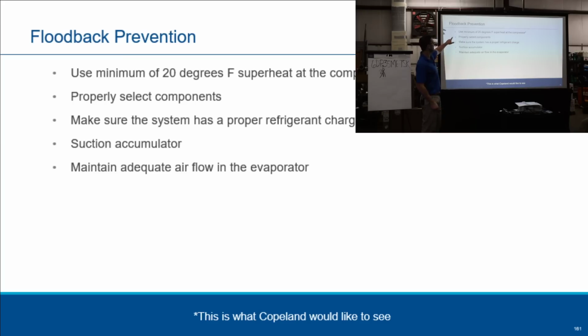Okay, things to prevent flood back. Copeland recommends 20 degrees superheat at the compressor. You can't always get 20 degrees superheat, right? If you have a small plate chiller with the TX valve or the electronic expansion valve, and you have 2 feet to the compressor and you're running at 10 degrees superheat, are you going to pick up 10 degrees superheat to that compressor? No, you're not, right? So, okay, it's running at 12 degrees superheat. As long as it doesn't go to 0 degrees superheat, we're good. But we would like to see 20.